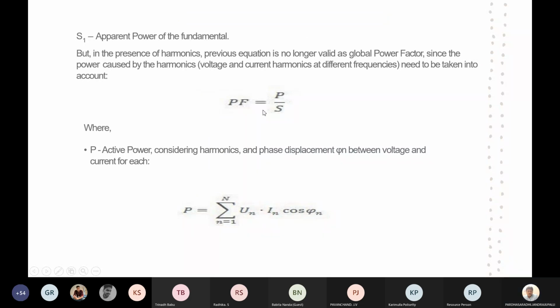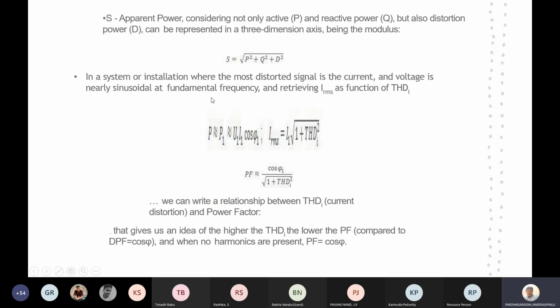Similarly, this power factor becomes P by S, where P is equal to sigma n equal to 1 to n of Vn In cos phi n. Usually S is the square root of P square plus Q square, the real power and reactive power. Whereas there is one more term to be considered, that is the distortion power. Thereby the power factor becomes cos phi 1 by square root of 1 plus total harmonic distortion square. What I want to convey is that the impact of harmonics is not only on other parts of the system, which can be seen as heat or other problems. It will be on the power factor too, as seen from these expressions.